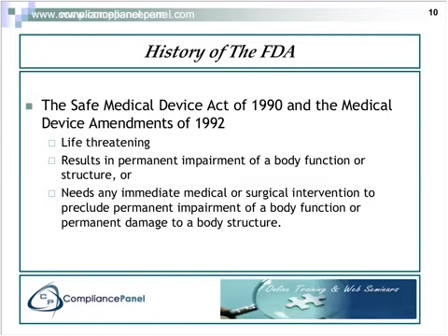The statute defines a serious illness or injury as life-threatening, or resulting in a permanent impairment of a body function or structure, or needing immediate medical or surgical intervention. If this happened related to your device, prior to 1992 you weren't required to report this to the FDA, but that's when this part was implemented.